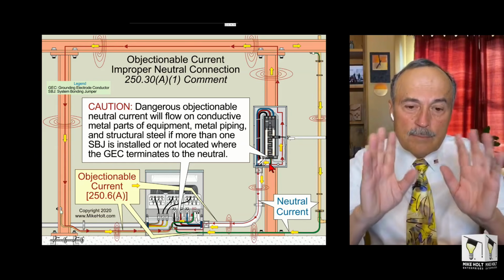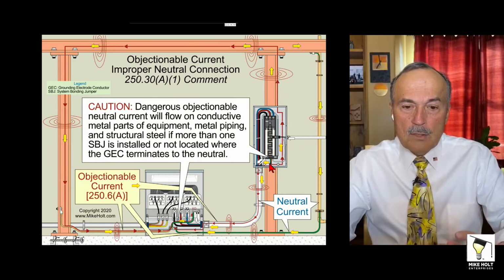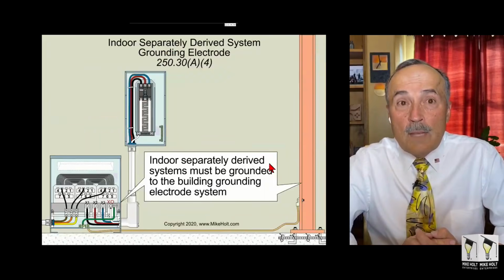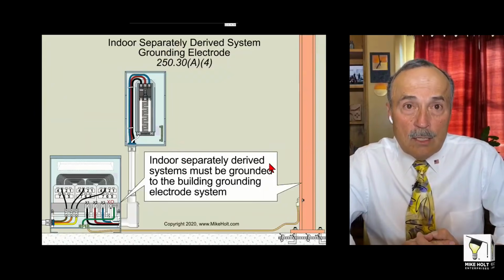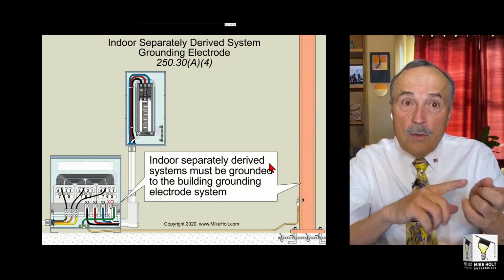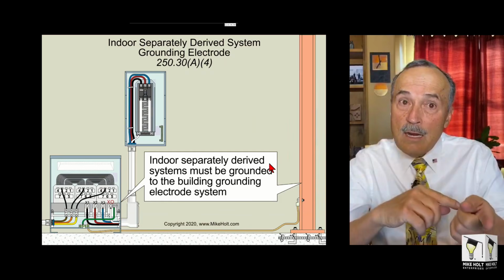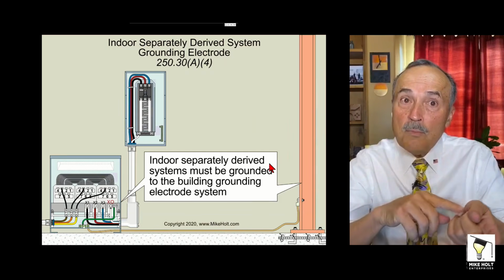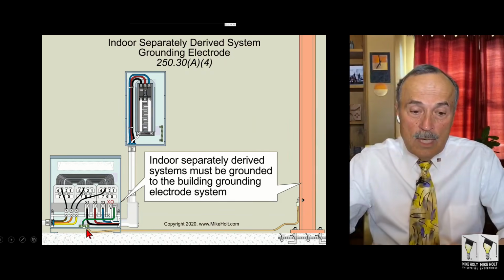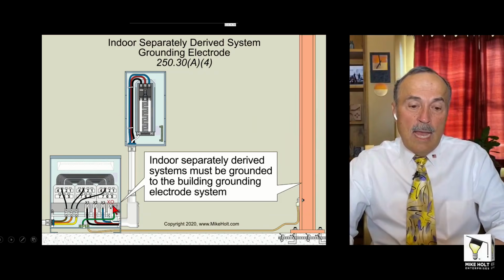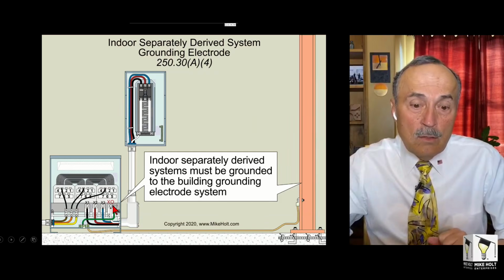It'd be a hazard. Again, it's not the place to talk about all the details. Where do you make the connection of the grounding electrode conductor? Well, you either make it at the transformer. The first disconnect means code doesn't care, but you'd have to put the system bonding jumper at the same location. Does that grounding electrode conductor have to be connected directly to the XO?